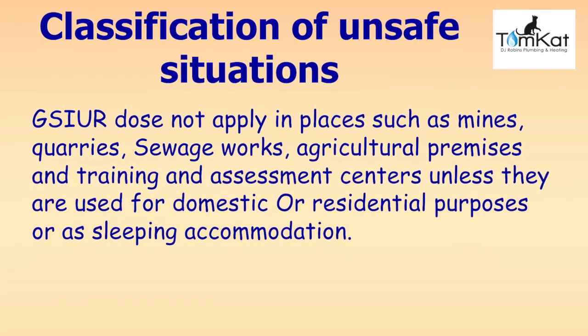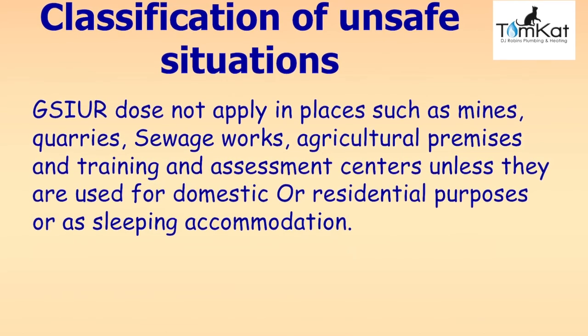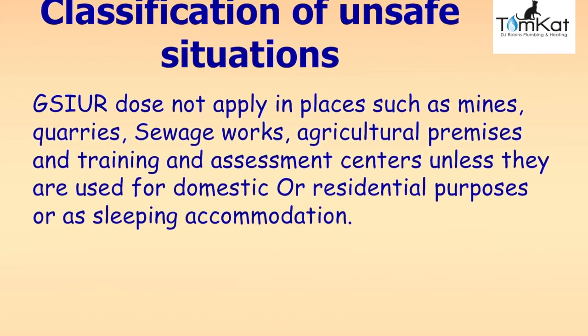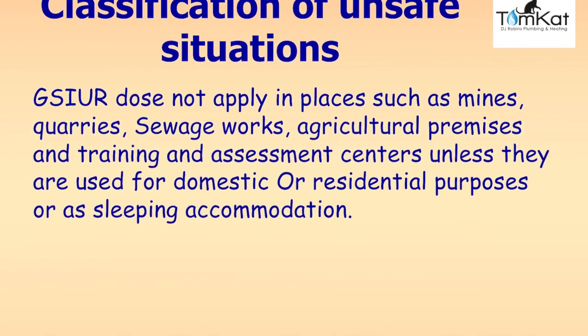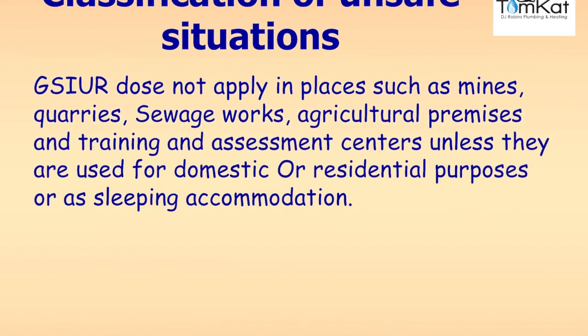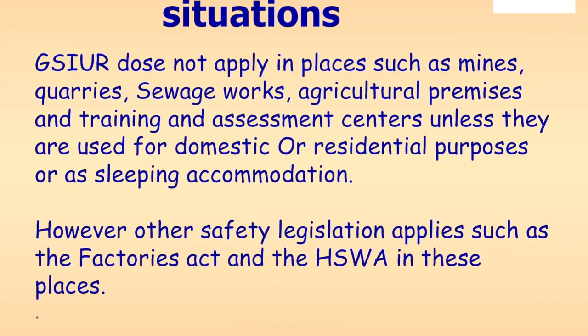The Gas Safety (Installation and Use) Regulations do not apply to places such as mines, quarries, sewerage works, agricultural premises, and training and assessment centres, unless they are used for domestic or residential purposes or as sleeping accommodation. However, other safety legislation applies in these places, such as the Factories Act and the Health and Safety at Work Act.